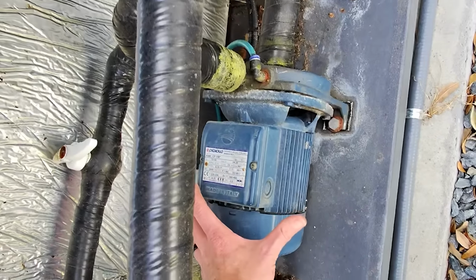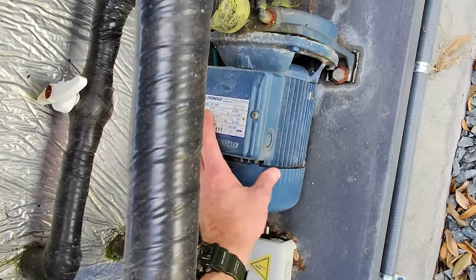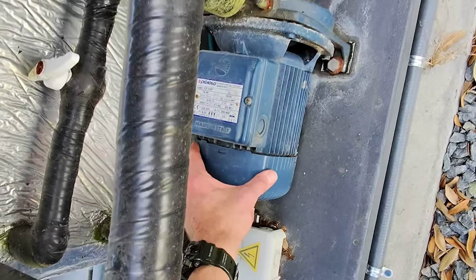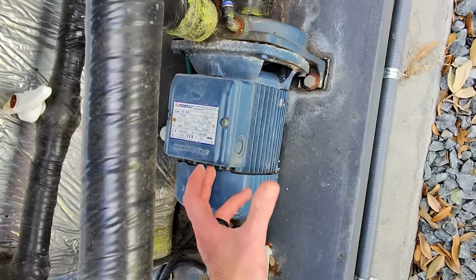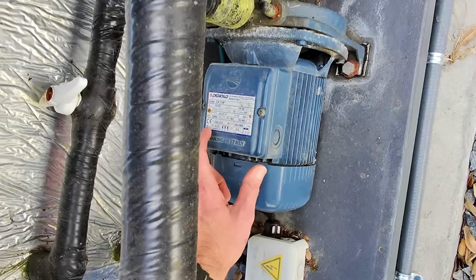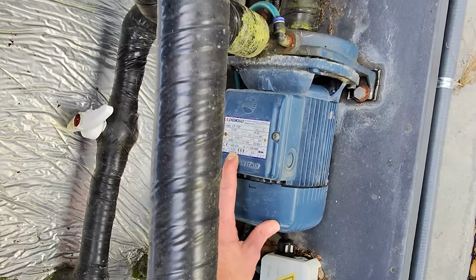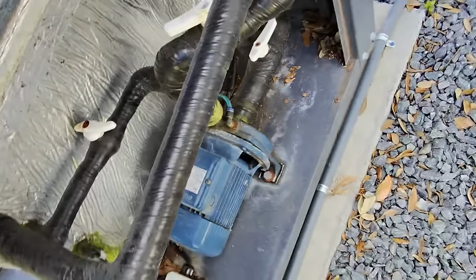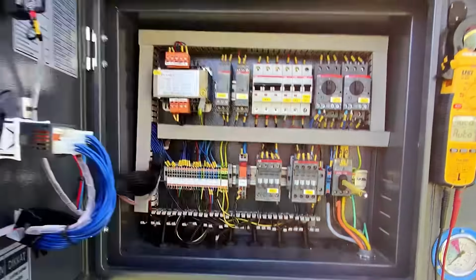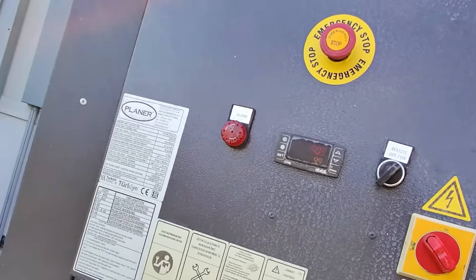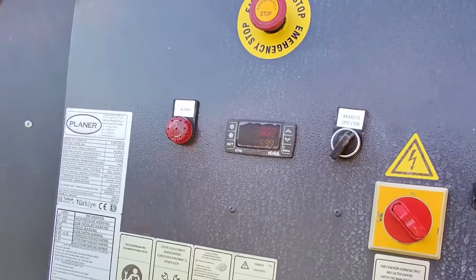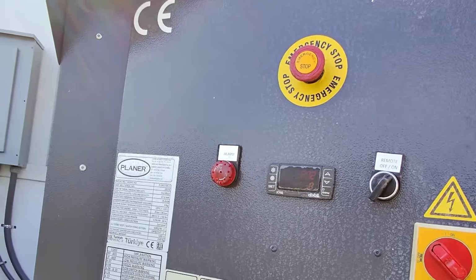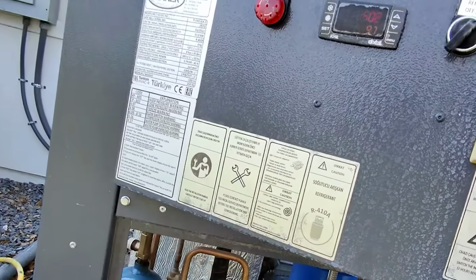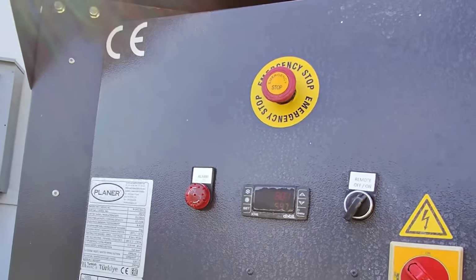Because remember, when we wire motors like this to the incorrect windings internally at different voltages, there's no telling, maybe we are wired for this, and that's why the amp draws are all over the place. Or out of range now. Man, am I having fun with this one. Okay, so update. Got the water pump to stop tripping, adjusting some parameters, increasing the amp draw rating that it's looking for on the motor.